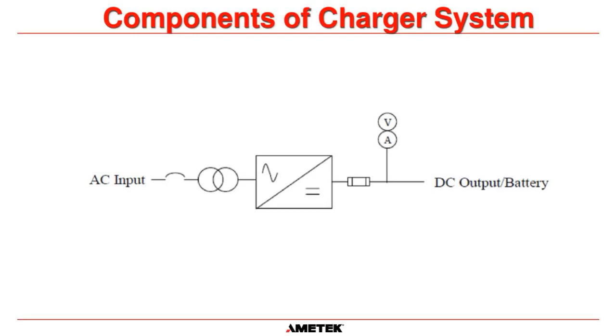Let's talk about the transformer first. Its main purpose is to step the grid AC voltage down to a level suitable for the DC output. The majority of chargers we deal with are connected to a 60-cell battery that needs to be float charged at around 135 volts DC.